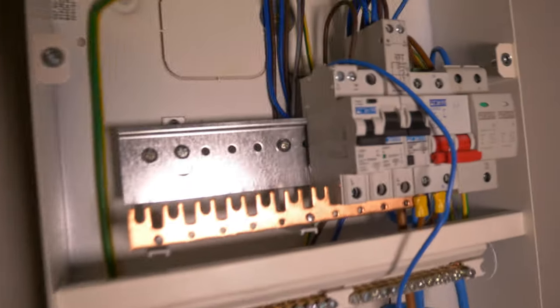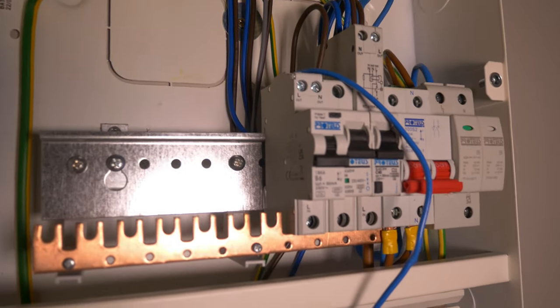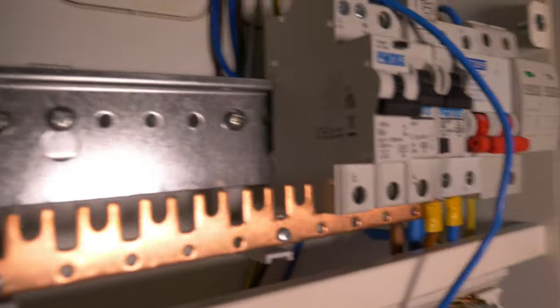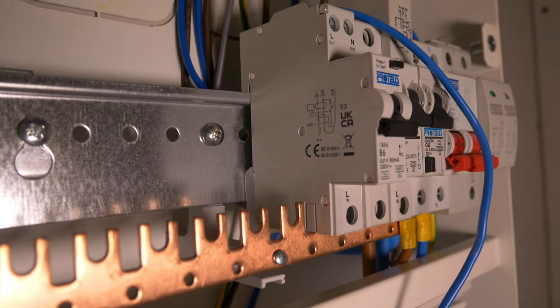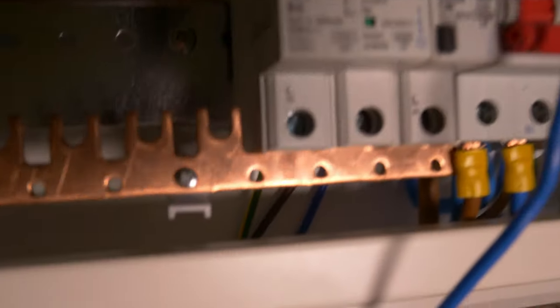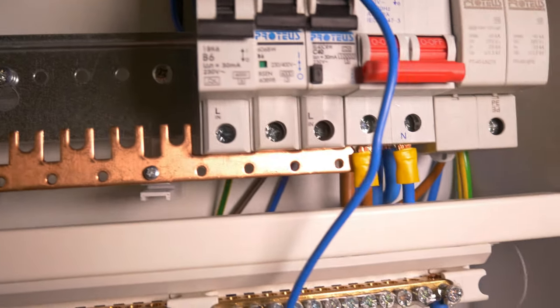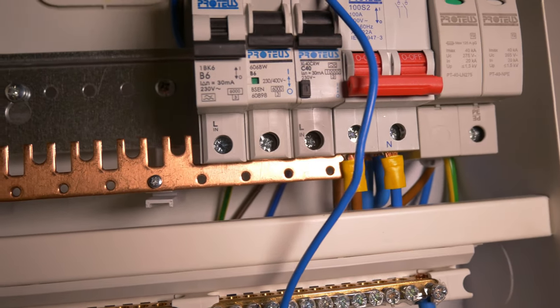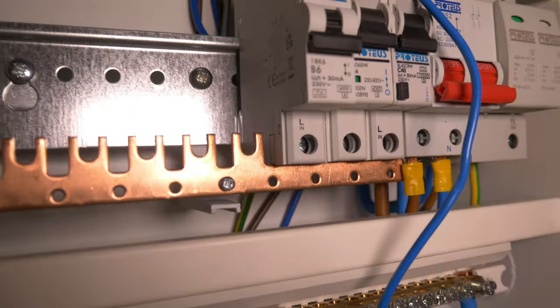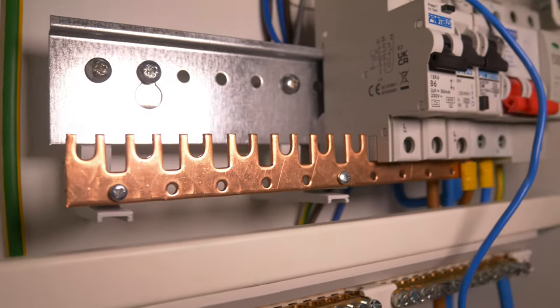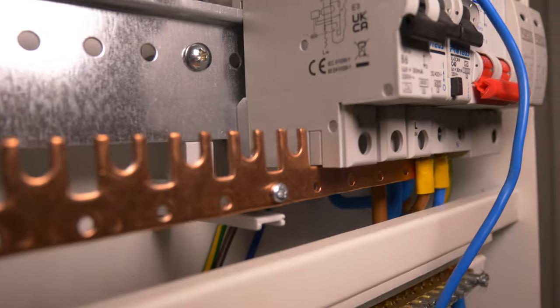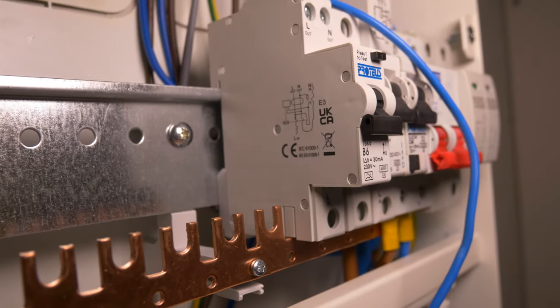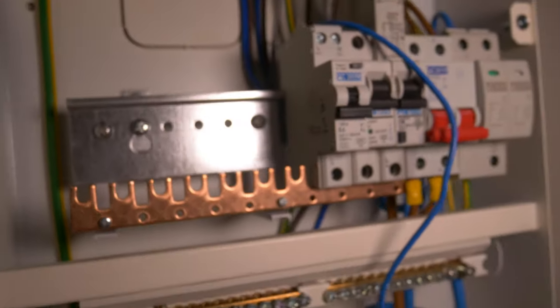The unique feature of these Proteus MCBs and RCBOs is they actually go on this front bus bar, as I would call it, rather than in a cage clamp. It's sitting behind the screw head, and it's impossible to enter those onto that bar incorrectly because they don't actually lock on underneath the DIN rail. You'd have to actually pull them up. So if you see on the back there, they're not locked in aside from the way they fasten on to the board. And I'll show you that in a second. We'll remove one and I'll demonstrate exactly what I mean.